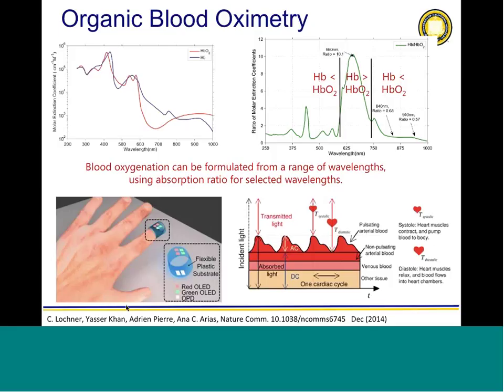Everybody knows that. It goes on the finger and clamps onto it. The reason it clamps is purely packaging, to block outside light from interfering with the measurement. The measurement is done with two LEDs, two light sources, and one photodetector. The light goes through the tissue, through the finger, and you measure the current in the photodiode on the other side. The reason you can calculate blood oxygenation from this is that if you look at the molar extinction coefficient of blood, there is a difference in absorption between the venous blood and the oxygenated blood.